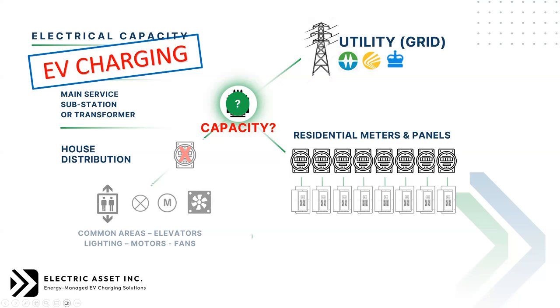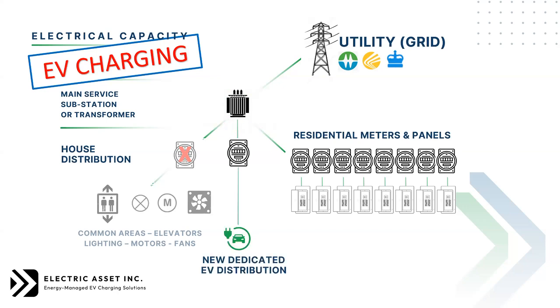So we're back on capacity of the main service. If there's capacity here, what needs to happen is we add a new meter, usually dedicated for EV charging, and put the EV distribution under a separate meter. This provides a second billing by hydro, covering all the EV distribution and charging in the building. Both work equally well, though the house system is preferable if there's adequate capacity.